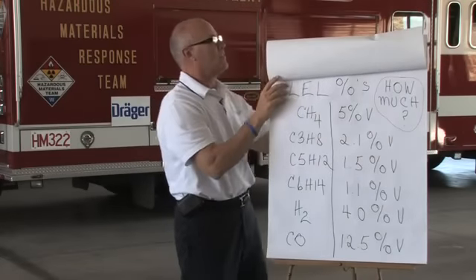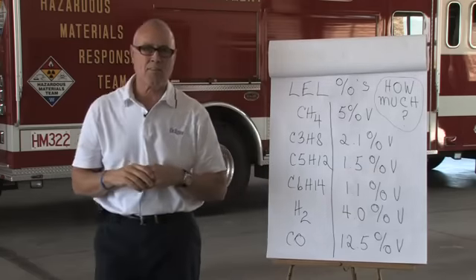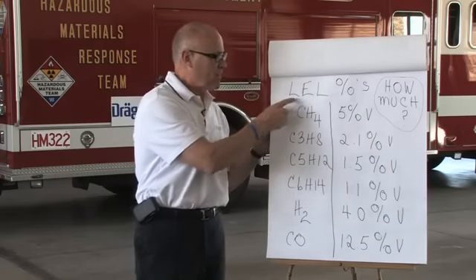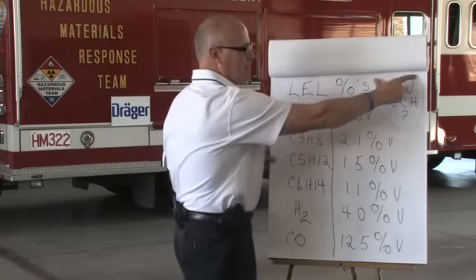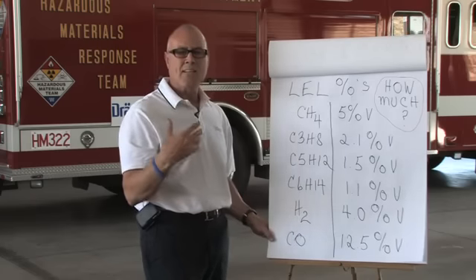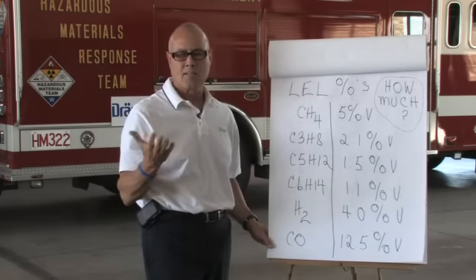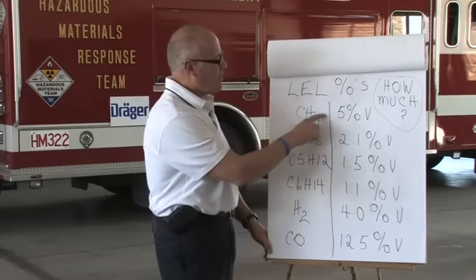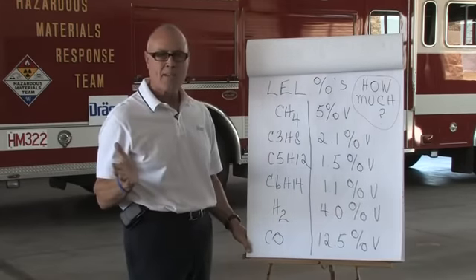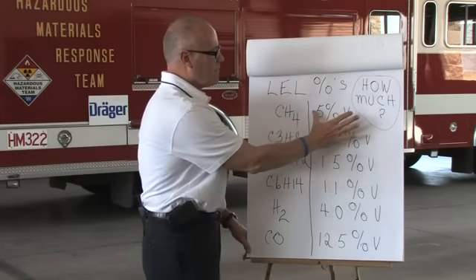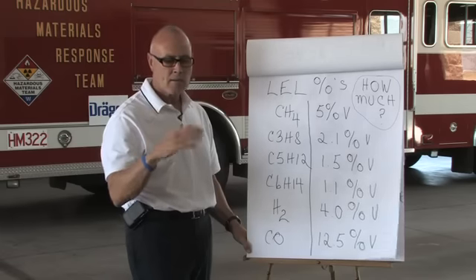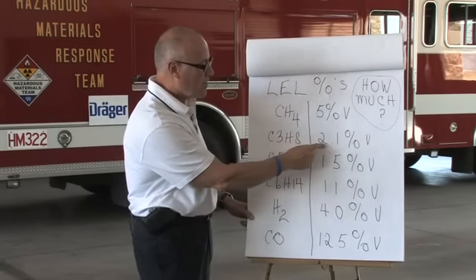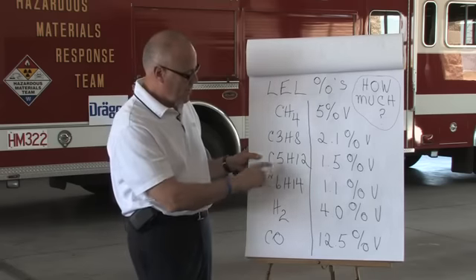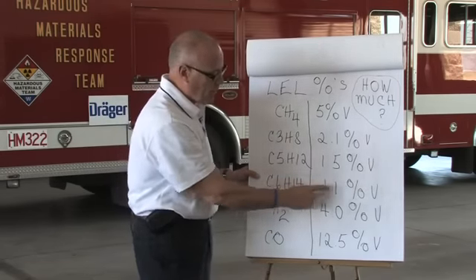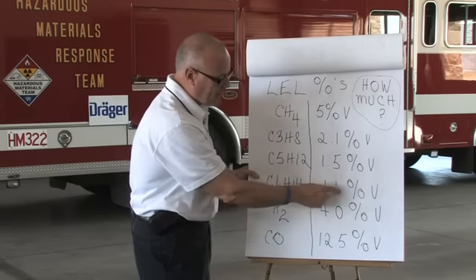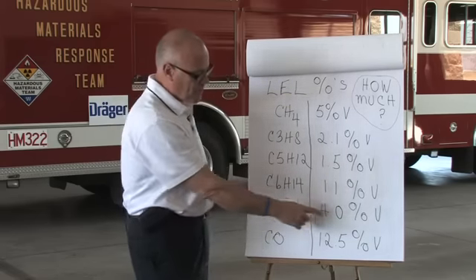And now I just wanted to show you that all combustible gases, whether they're a gas or a vapor, all have different lower explosive limits. And what I mean by that is exactly this. How much gas does it take before you have to have an ignition source and oxygen to create a combustion or an explosion? So you can see here's our typical methane that we've all been talking about, our natural gas, our methane, our CH4, 1 carbon, 4 hydrogens. 5% by volume is what we need to light the match, kaboom, okay? Here's propane, you only need 2.1% by volume for the explosion to occur. Here's pentane at 1.5% by volume. Here's hexane at 1.1. This is very similar to that of gasoline. Gasoline's LEL, I believe, is about 1.3, pretty close to that marker. Here's hydrogen at 4% by volume.